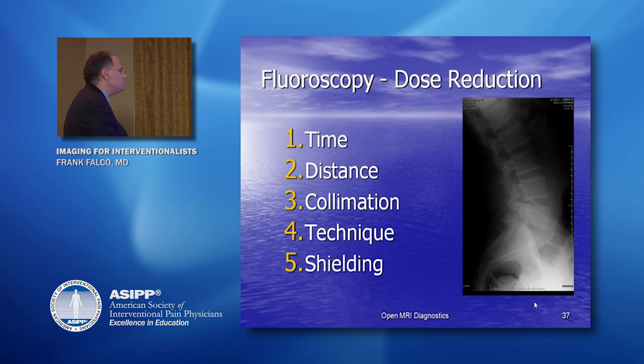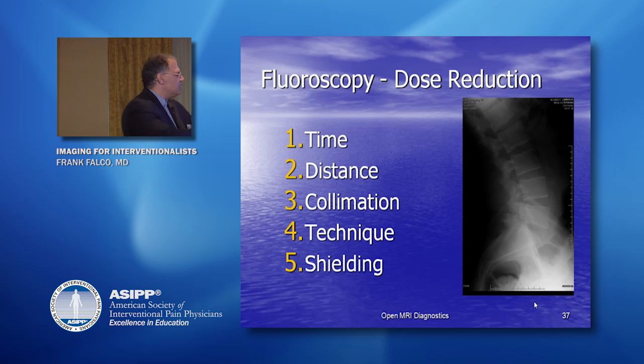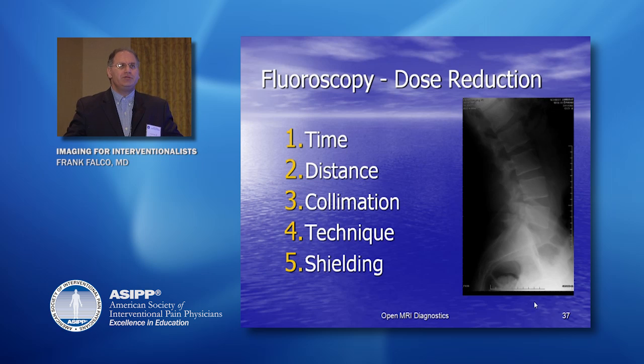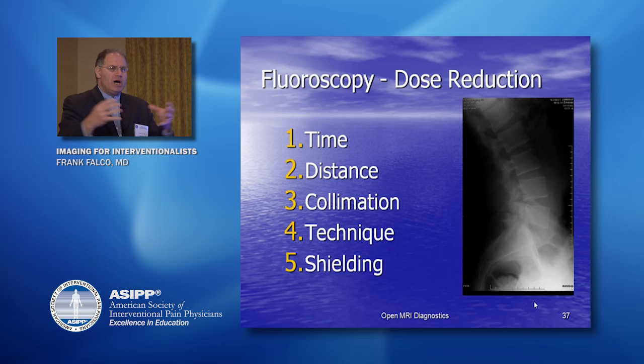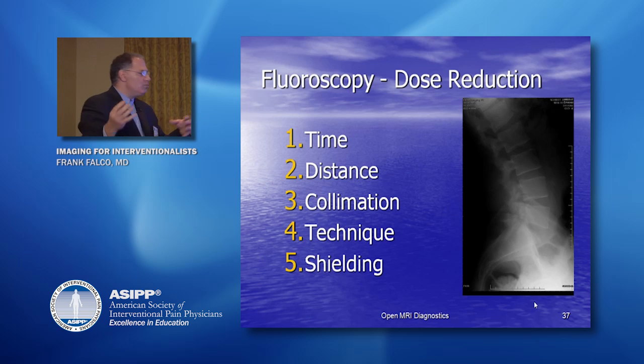Fluoroscopic dose reduction, really important. These are the 5 things. So if there's one thing you take away from the lecture, it's this slide. You can throw everything out, save this slide: time, distance, collimation, technique, and shielding, right? So the more time that you have the C-arm on, is there more radiation exposure or less? More, okay? If you stand further away from the C-arm, I'm over here, am I exposed to more radiation or less? Less, okay. Collimation, and you saw that diagram, we went back and forth.